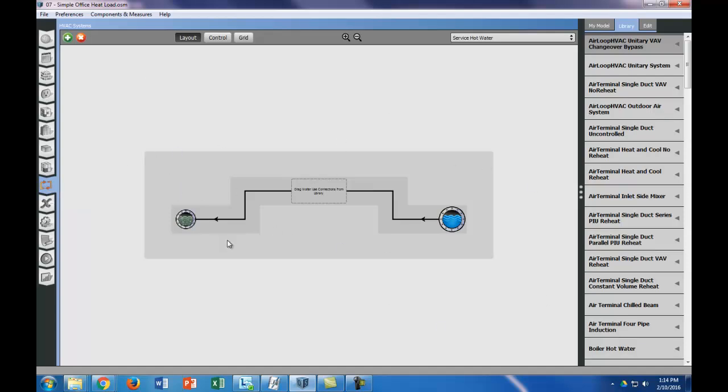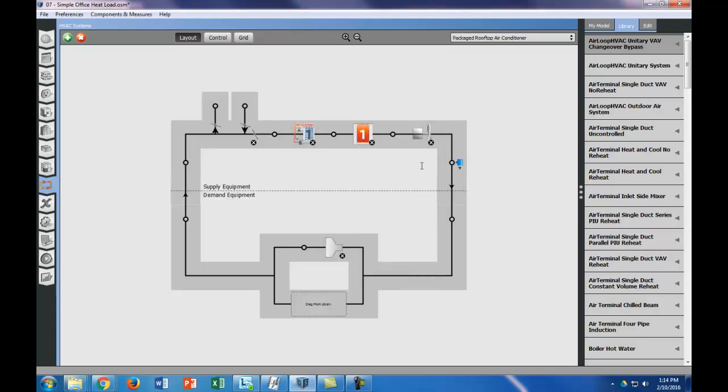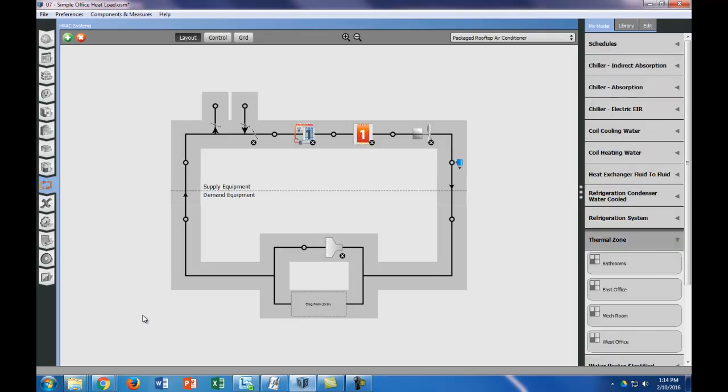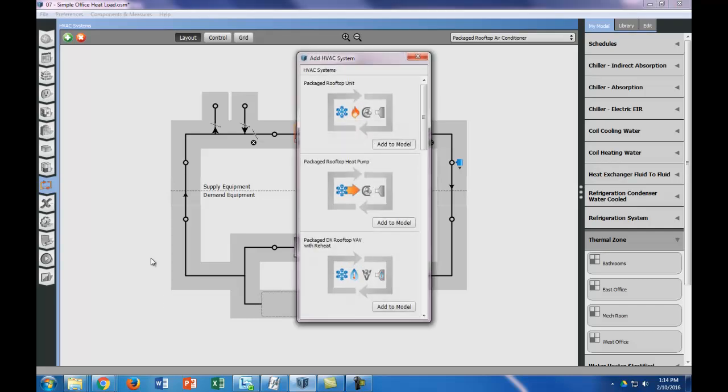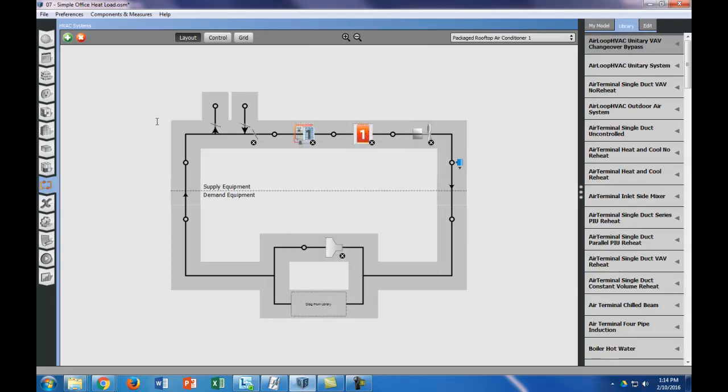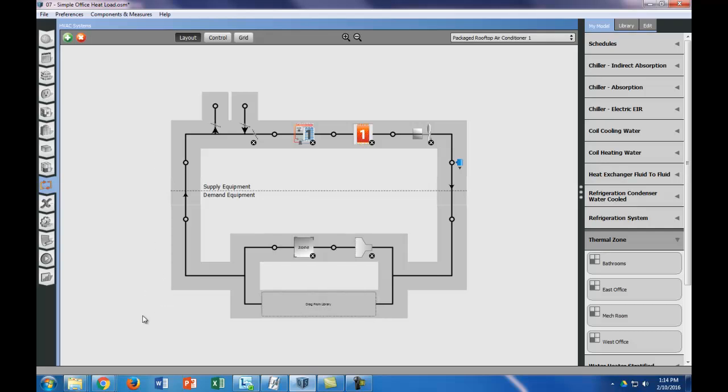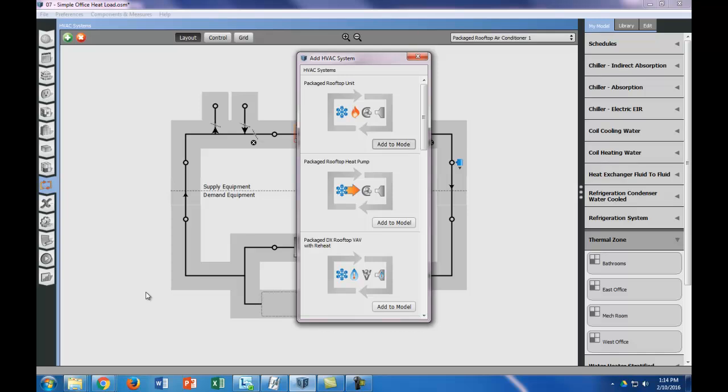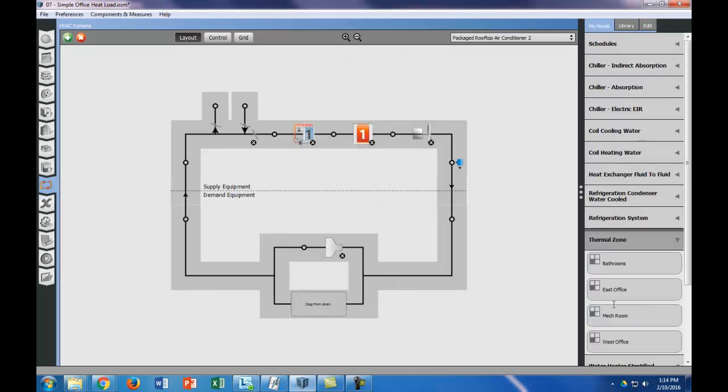We'll put in just HVAC systems to serve this area, or these three areas. So what I would recommend is that we just make three packaged rooftop units, the easiest thing we can have, and they have cooling, it's just a heat pump for cooling, and then natural gas. And we're going to add that to our model. And then we're going to basically go to our thermal zones and make one of these for each thermal zone, except for the mechanical room. So we'll do the bathrooms first, so that's going to be just packaged rooftop air conditioner. Then we're going to make another one, and then we're going to go back to our thermal zones and do east office. And we're going to go back and go back to our thermal zones and go to west office.